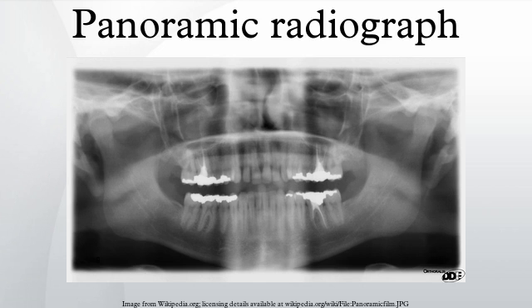Normally, the person bites on a plastic spatula so that all the teeth, especially the crowns, can be viewed individually. The whole orthopantomogram process takes about one minute. The patient's actual radiation exposure time varies between 5.5 and 22 seconds for the machine's excursion around the skull. The collimation of the machine means that while rotating, the X-rays project only a limited portion of the anatomy onto the film at any given instant.